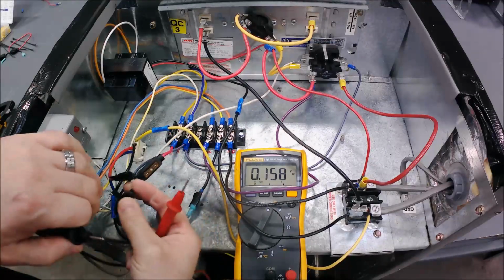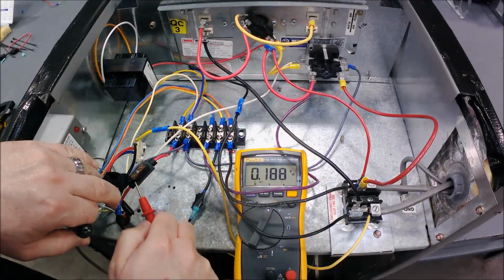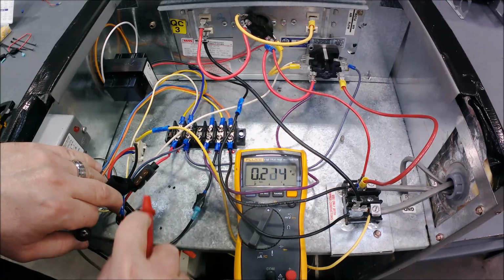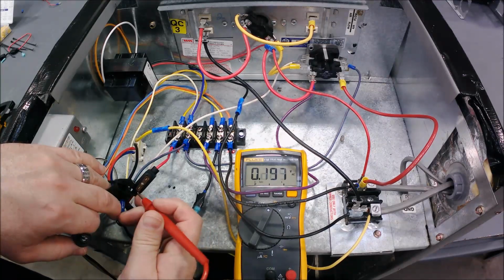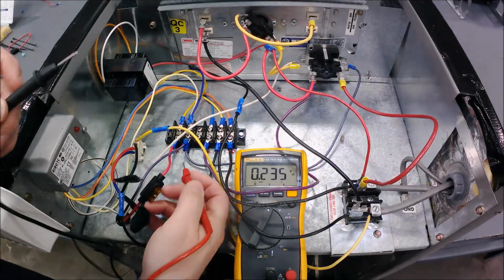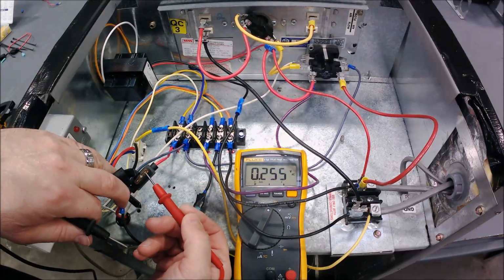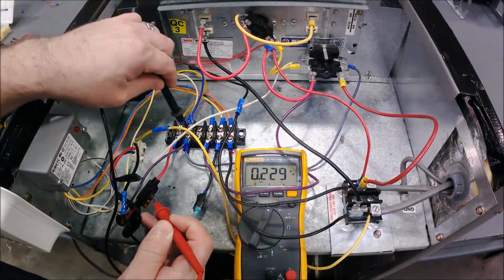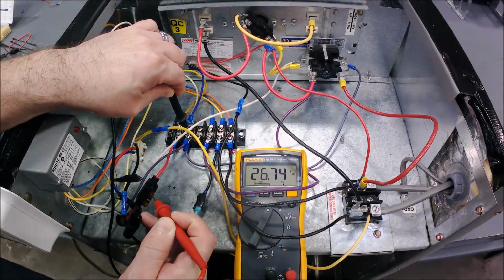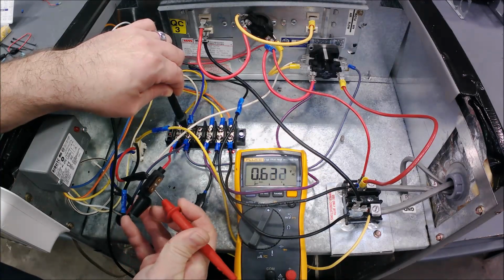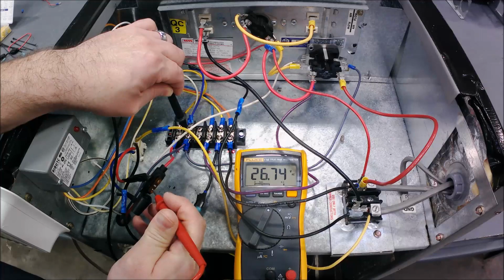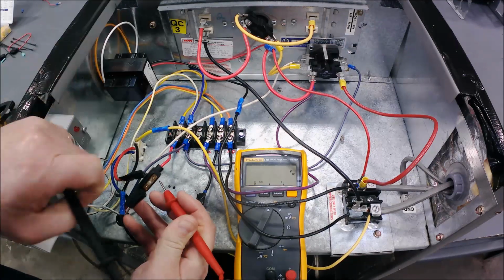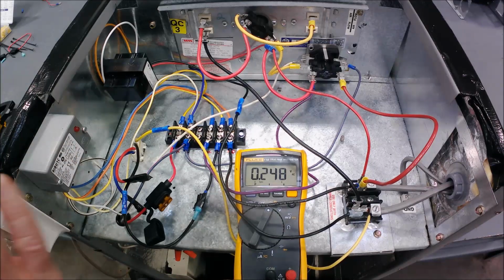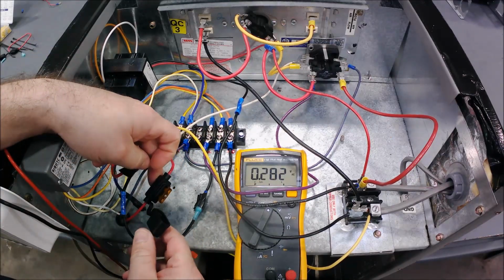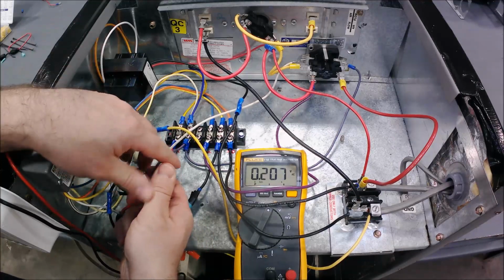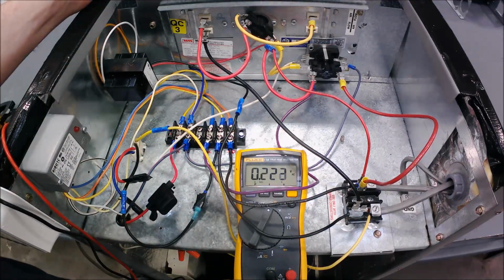I don't know how many people pay attention, but right here to the left and right of that 5 amp fuse number is a bare piece of metal. If you were ever checking a fuse to see if power was passing across, I know that as I read it here, power comes in on this side. So if I'm checking there, I can get my 24 volt, and it tells me. But I can leave the fuse in play and check to see if power came out on that side of the fuse. So don't neglect those two little indentations where they give you a bare piece of metal. But that's a rib relay. It's really nothing different than a 9340 if you buy the proper one.